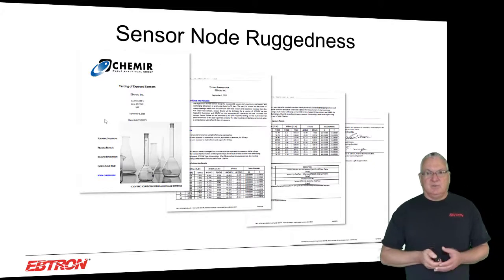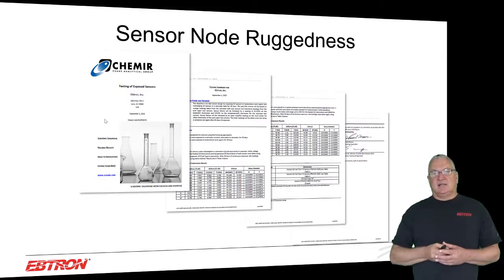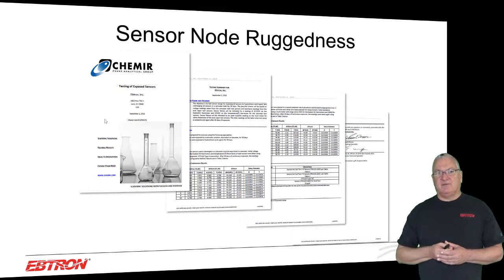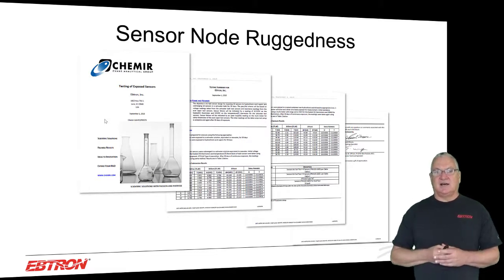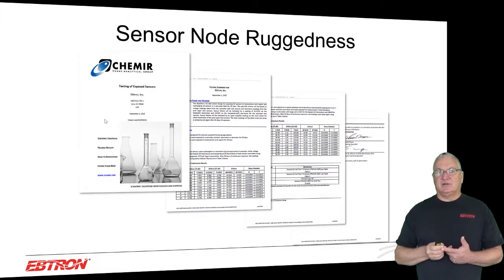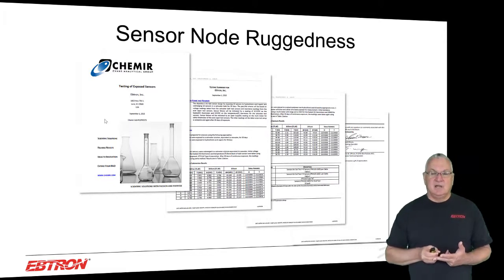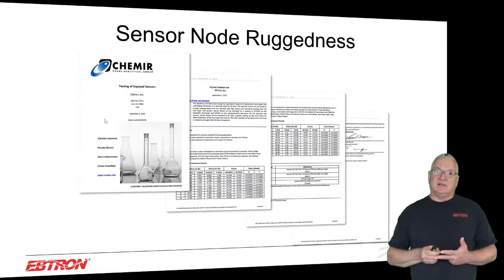The other thing that's real important with us, I think, is what we call sensor node ruggedness. We've been around for a long time. I think we've gone to the College of Hard Knocks in that time. And we learned that outdoor air intakes in particular are not clean. There's a lot of exposure to salts, and to atmospheric acids, a lot of sulfur dioxide in the atmosphere. And we learned the hard way over the years that you could get corrosion of the sensors.